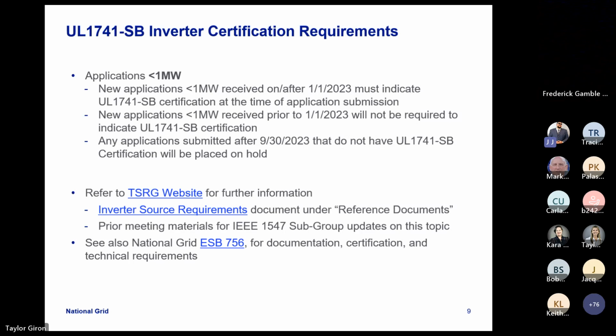For any applications less than a megawatt, National Grid will begin requiring that every inverter that is non-CHP generating equipment be UL 1741 SB certified. The SB supplement is an updated version that incorporates the additional testing requirements found in IEEE 1547. Any applications submitted after September 30th, or on October 1st, will require that SB 1741 certification for all proposed equipment. If that's not provided, those projects will be placed on hold. Please refer to our TSRG website for further information, inverter sourcing requirements, and our ESB 756 for all those additional technical requirements.